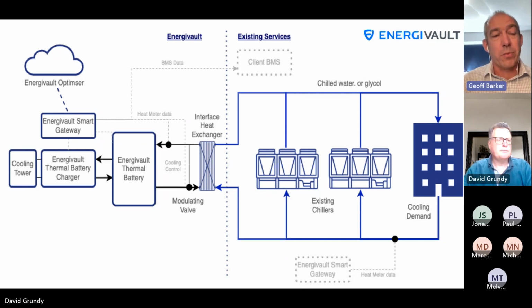So the EnergiVault effectively comprises three main elements, if you ignore the cooling towers as a fundamental part of the refrigeration: a thermal battery, which is a volume containing the ice slurry, the latent energy; a thermal battery charger, which is the primary refrigeration plant - in the current case an ammonia system; and an EnergiVault smart gateway, which provides the interface for control both to external cloud-based optimizers, our developments in the EnergiVault platform, and also connecting to the client's BMS, which is still dominant in terms of how things are controlled, but we'll come on to that later.